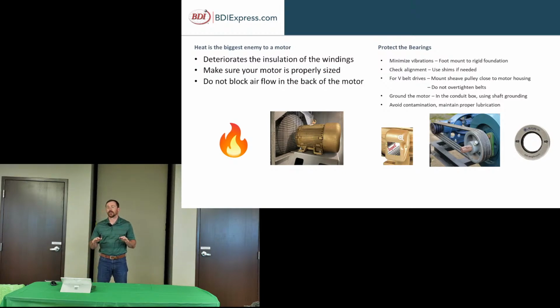What Tim had mentioned, alignment: if you need to use shims, you can, to keep it properly aligned. If you're out of alignment, you're going to cause wear. If your belts are applying tension in a different direction, or you picture holding a beer mug with your weight far away from you, that is called overhung load, which causes quicker wear for the bearing. You want to have that stuff mounted as close as possible while keeping it aligned, to reduce the odd loads those bearings are going to see. So mount your sheaves as close as you can while maintaining that alignment. Also ground your motor to the conduit box, and you can also use shaft grounding rings. And the number one cause of bearing failure is contamination and maintaining proper lubrication.